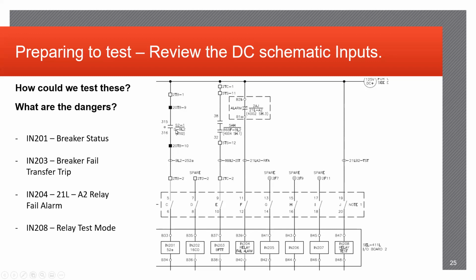identifying the operation of your BL2 breaker. This 52A contact determines whether the breaker is either open or closed, and you need to correctly identify that to the input of the relay. So going a little more in depth into that, this 52A is associated directly from the breaker itself, identifying whether it's open or closed. So if the polarity on this is opposite of what the relay is seeing, that could cause immense issues, especially when you go to restore the relay and put it back into service.